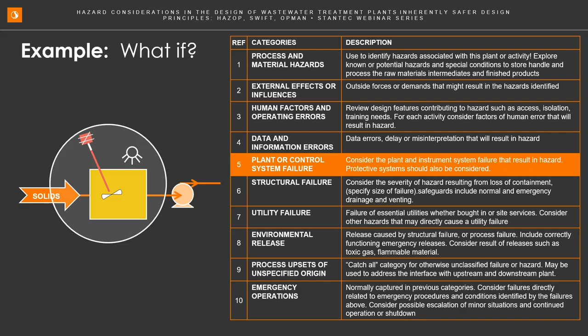And in this case, they came up with 2 what-ifs. What if the level sensor is out of calibration? Well, then we don't know if there's a high or low level in the tank. Now, these tanks act in parallel, and they have a pipe that connects them with an isolation valve. Well, they said, okay, the safeguard was to use the level sensor in the other tank because the level in the 2 tanks should be the same, and they have a backup level switch. However, the team said, hold on a minute. What if you've closed that isolation valve because you got a tank offline? You have that isolation valve closed and the levels aren't the same. So then they said, well, you need to have a position indicator and you need a discrepancy alarm.